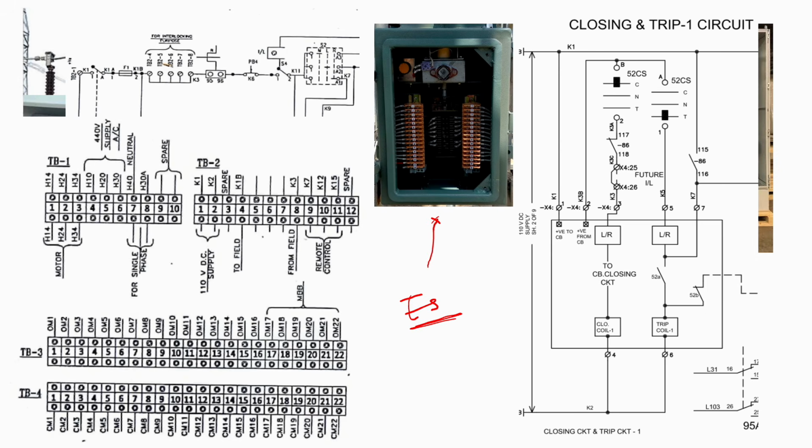We use earth switch for earthing purpose. For any shutdown or maintenance time, we need to earth our equipment over our transmission line or our elements. So in line isolator we have earth switch as well, so you can make earth switch as an interlock as well. For that, in the earlier stage the same principle we used: 21 connections were connected at TB 425 and 22 was connected at 6. So this directly connects our isolator with the breaker.